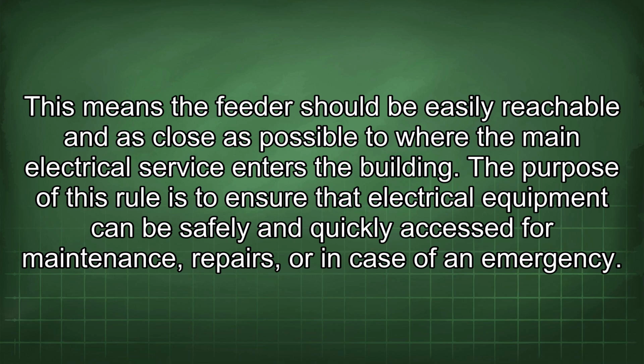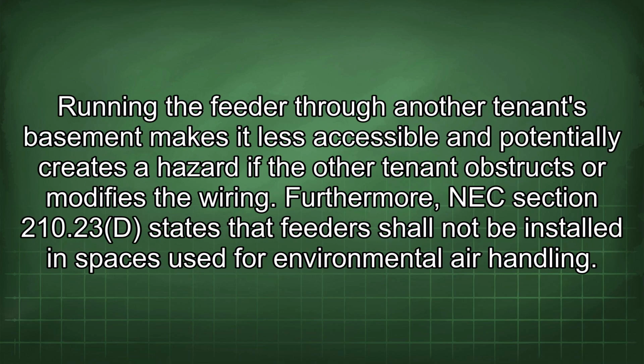The purpose of this rule is to ensure that electrical equipment can be safely and quickly accessed for maintenance, repairs, or in case of an emergency. Running the feeder through another tenant's basement makes it less accessible and potentially creates a hazard if the other tenant obstructs or modifies the wiring.